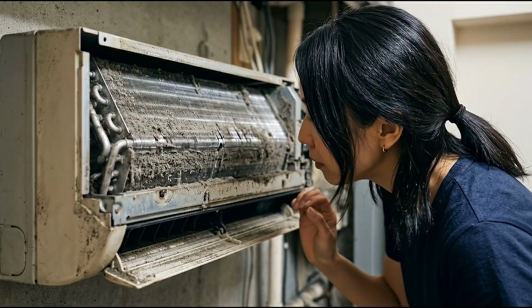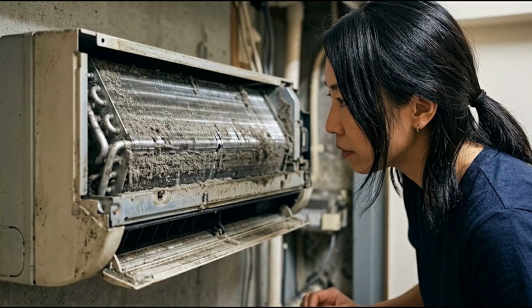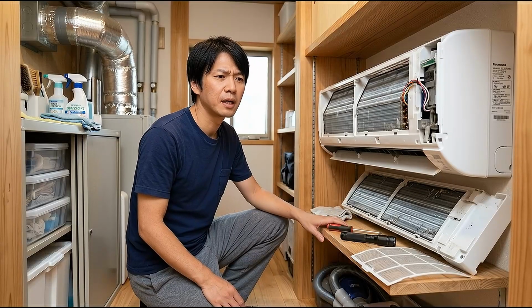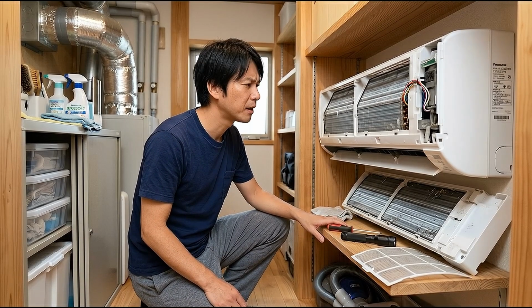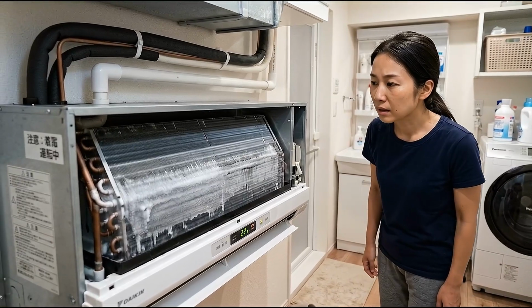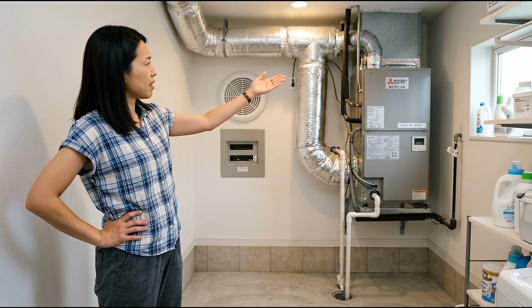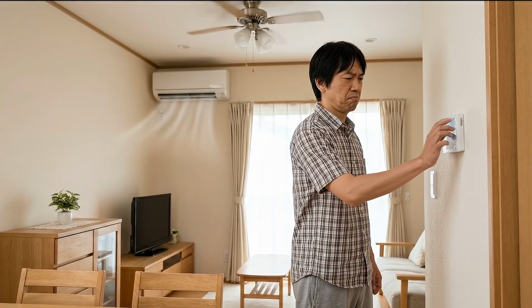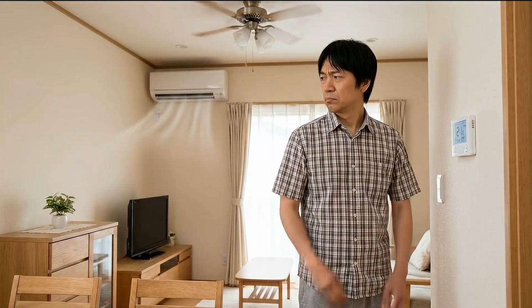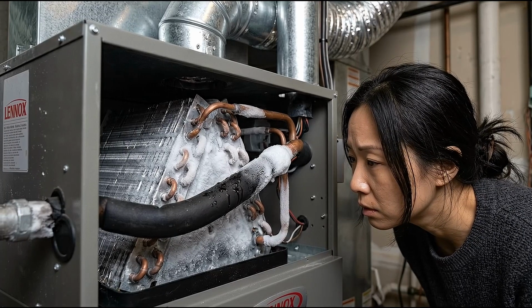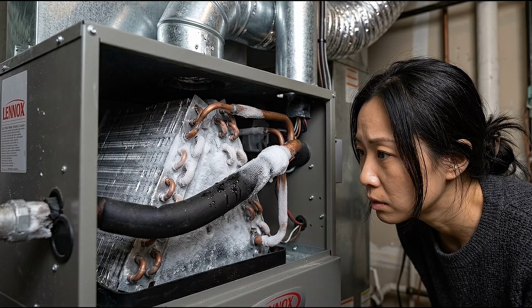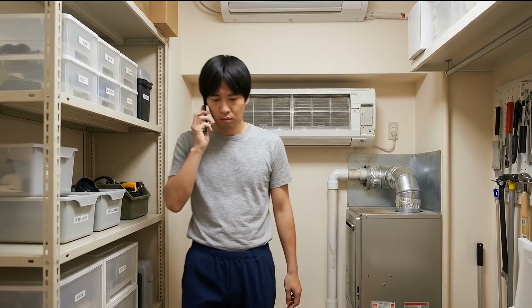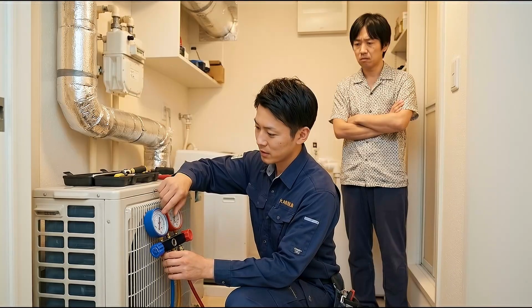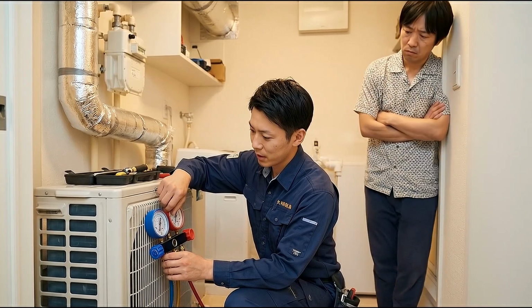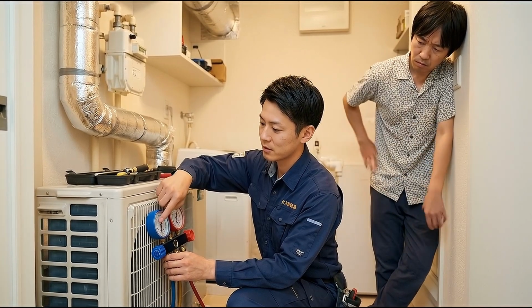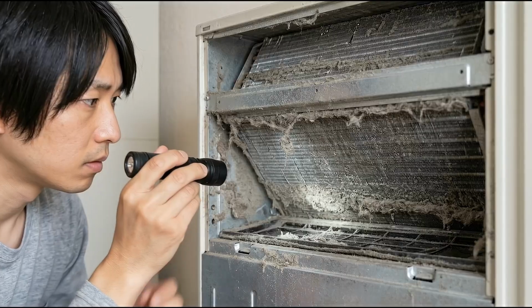The reason that line is important is that dirty coils and clogged filters produce symptoms that look identical to low refrigerant. Both cause the evaporator coil to run too cold. Both produce weak airflow. Both make the system run longer cycles without reaching the set temperature. Both can cause ice to form on the coil or the refrigerant line. A homeowner who calls a technician without cleaning the system first is at risk of paying for a refrigerant recharge that does not fix the underlying problem because the underlying problem was dirt, not gas.